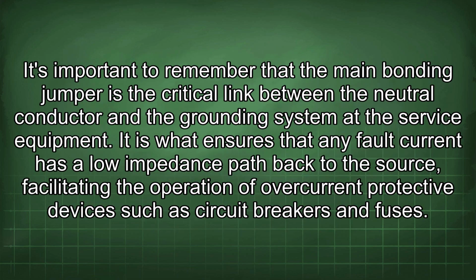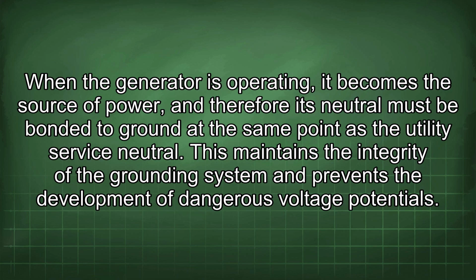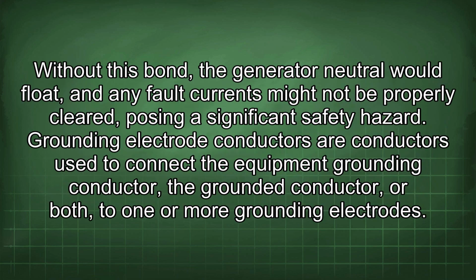It's important to remember that the main bonding jumper is the critical link between the neutral conductor and the grounding system at the service equipment. It is what ensures that any fault current has a low impedance path back to the source, facilitating the operation of overcurrent protective devices such as circuit breakers and fuses. When the generator is operating, it becomes the source of power, and therefore its neutral must be bonded to ground at the same point as the utility service neutral. This maintains the integrity of the grounding system and prevents the development of dangerous voltage potentials. Without this bond, the generator neutral would float, and any fault currents might not be properly cleared, posing a significant safety hazard.